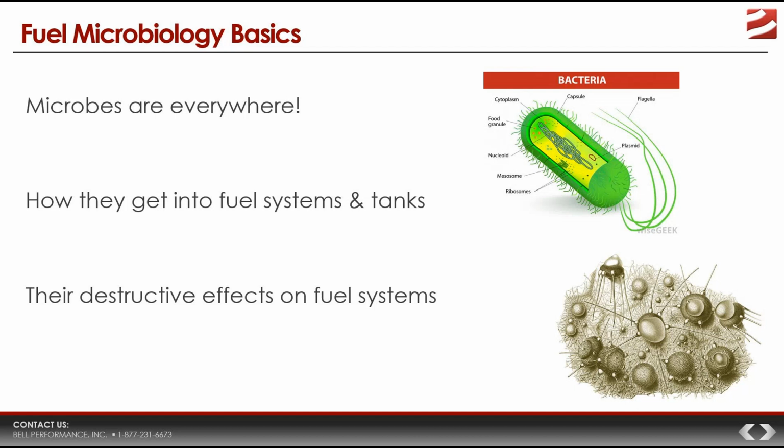Now, for storage tanks, there's lots of ways that they can get in there. Basically, anything that enters the storage tank has some level of microbial growth associated with it. Whether you're talking about free water ingress from leaks or from spill buckets, even things like water vapor and just dust that's on the air that goes in and out of the vents, and of course, fuel drops. Anything like that, you can have fuel microbiological inoculation, so to speak.